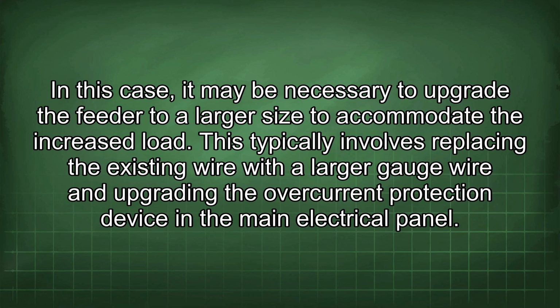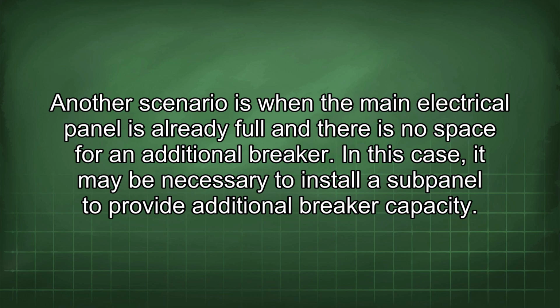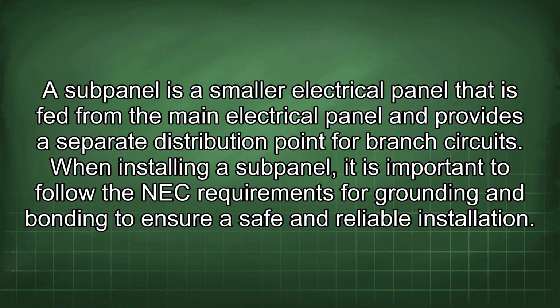Another scenario is when the main electrical panel is already full and there is no space for an additional breaker. In this case, it may be necessary to install a subpanel to provide additional breaker capacity. A subpanel is a smaller electrical panel that is fed from the main electrical panel and provides a separate distribution point for branch circuits. When installing a subpanel, it is important to follow the NEC requirements for grounding and bonding to ensure a safe and reliable installation.